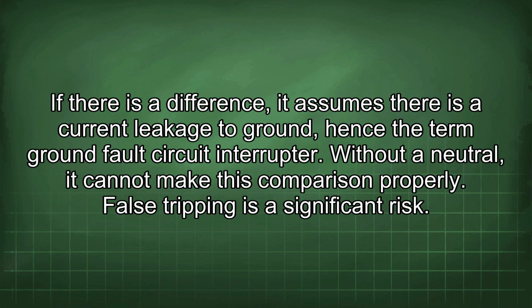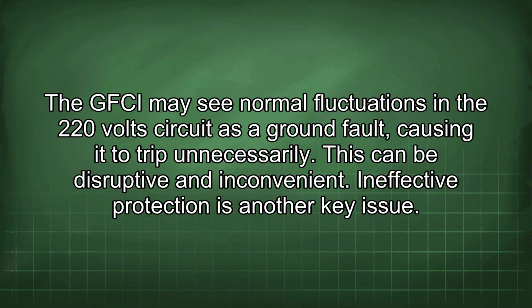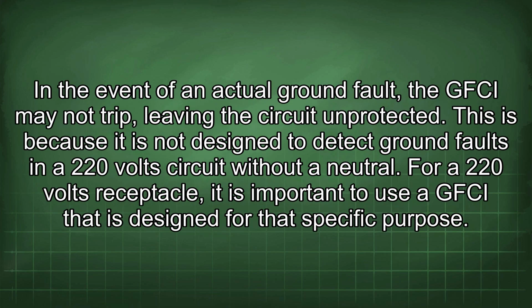False tripping is a significant risk. The GFCI may see normal fluctuations in the 220-volt circuit as a ground fault, causing it to trip unnecessarily. This can be disruptive and inconvenient. Ineffective protection is another key issue. In the event of an actual ground fault, the GFCI may not trip, leaving the circuit unprotected. This is because it is not designed to detect ground faults in a 220-volt circuit without a neutral.